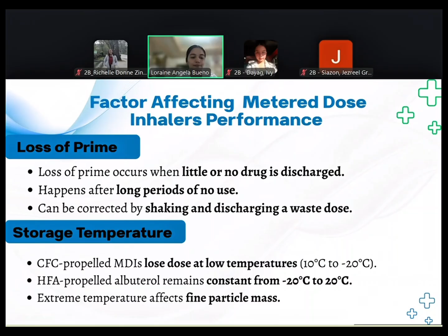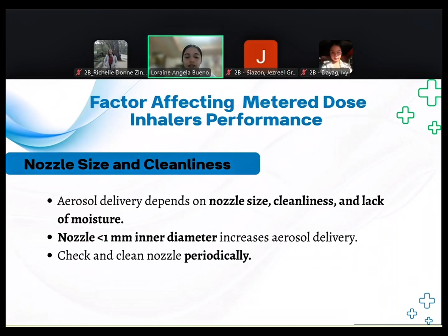Sa storage temperature naman, sa CFC propellant metered dose inhaler, lose dose at low temperature at 10 to -20 degrees Celsius, and HFA propellant albuterol remains constant from -20 to 20 degrees Celsius. Extreme temperature affects the fine particle mass. So, nozzle size and cleanliness naman. Aerosol delivery depends on the nozzle size, cleanliness, and lack of moisture. Nozzle less than 1 mm inner diameter increases aerosol delivery. Check and clean the nozzle periodically.